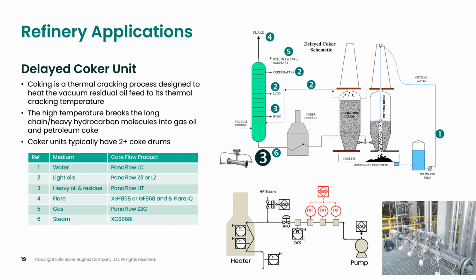For lighter oils such as naphtha and LCGO, we use either our Panaflow Z3 or LZ process-wetted ultrasonic flow meter. For the flare lines, we use our XGF868I flare meter. For the fuel gas, we would use our Panaflow Z2G process gas meter. For the steam lines, we would use our XGS868I ultrasonic flow meter. However, the measurement that this slide focuses on is the heavy oil feed line into the furnace.